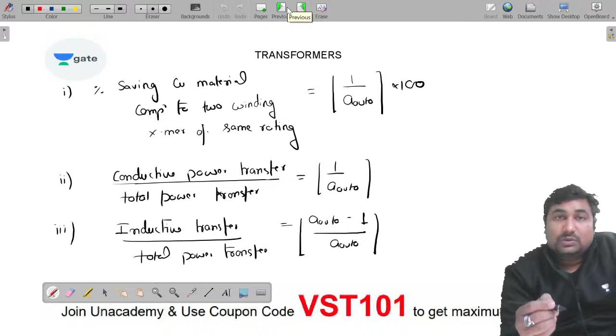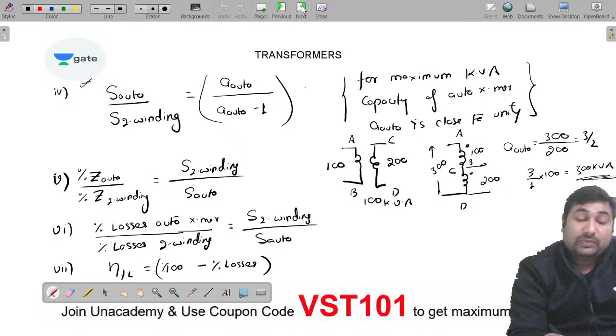Short circuit current, please observe here, the per unit short circuit current is very high in case of an auto transformer compared to a two winding transformer when the same two winding transformer is connected as an auto transformer, because of the fact that the percentage impedance is lower. Is it okay? So short circuit current is inversely proportional to the percentage impedance. Percentage impedance is decreasing and therefore this per unit short circuit current is increasing. Is it okay? So it means fault level is increasing.